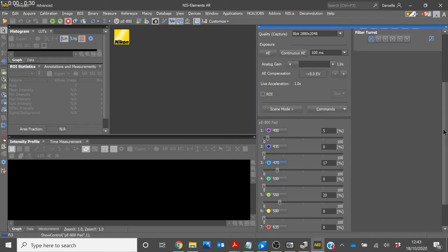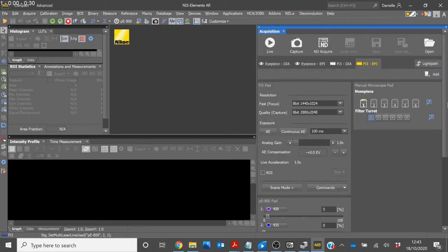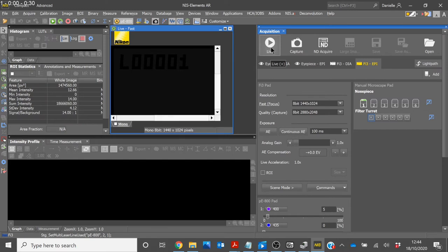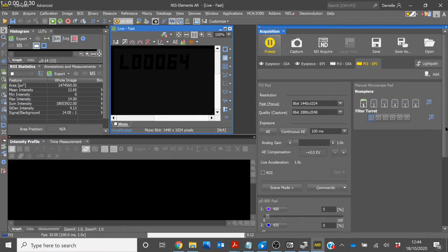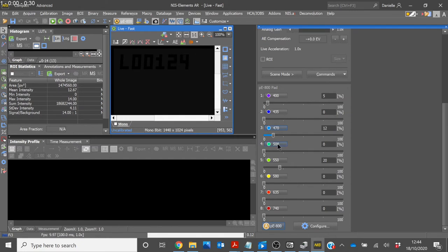If you simply want to go live, all you need to do is select the intensity of the wavelength you require, select the LED itself. You will see here it is highlighted blue. Scroll up, select Live and you will see that the LED will be illuminating. Whilst you are in live, you are then able to adjust the intensity in real time and switch on additional LEDs as required.